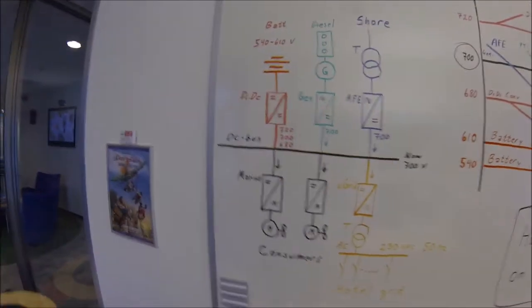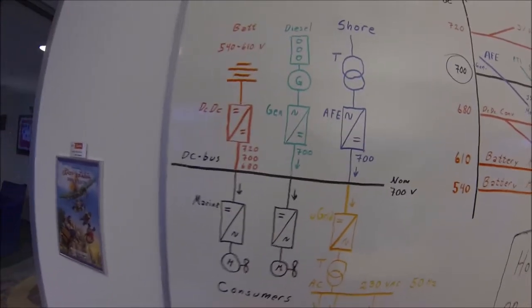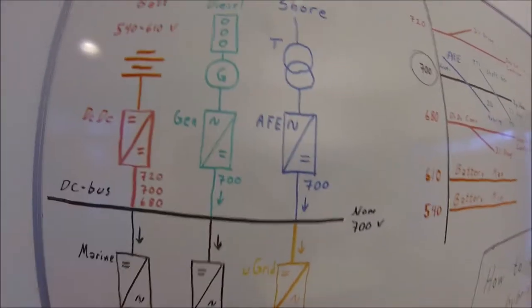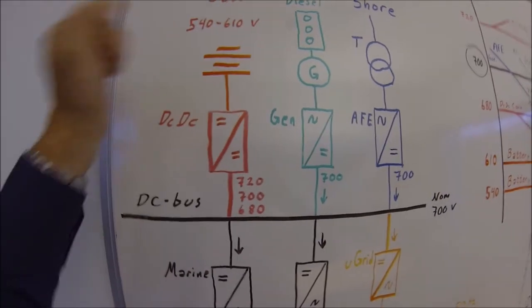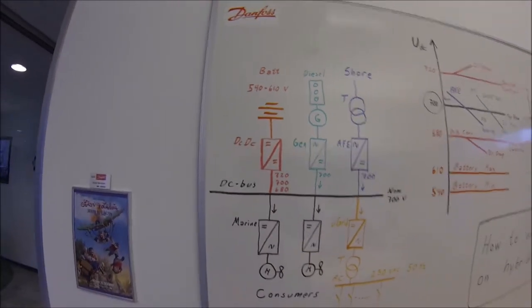However, the speed you need to control it might be a challenge because you have to do it within 10 milliseconds. When you have a power demand here, then these ones have to feed in the energy very fast. So if you also have the speed handle here from the battery, it doesn't work fast enough in the PLC world.